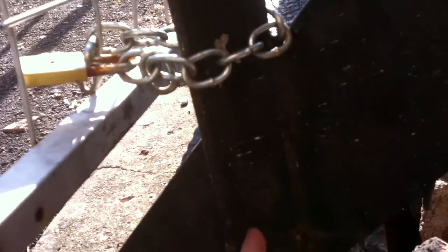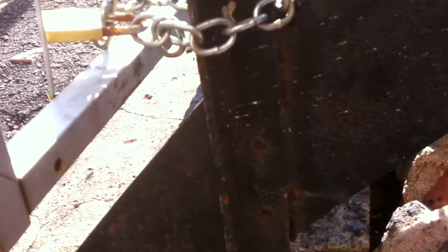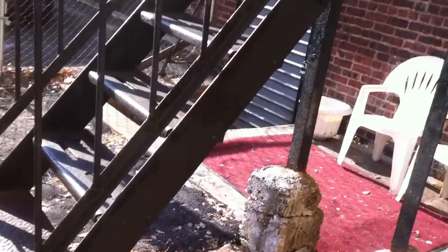They got bolts missing. So, if somebody comes in here and just rebolts this, is that a satisfactory repair? And never removes the rust? No. They must remove the rust. If they don't remove the rust, but they bolted it, it's not a satisfactory repair. You got to remove the original cause of the violation.